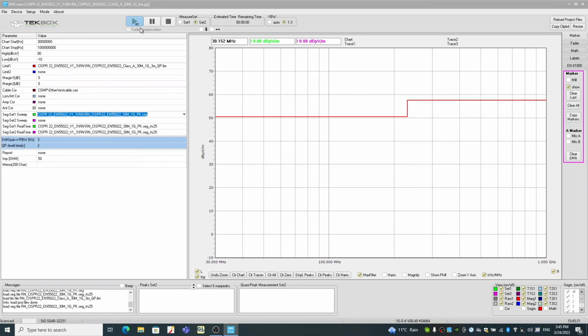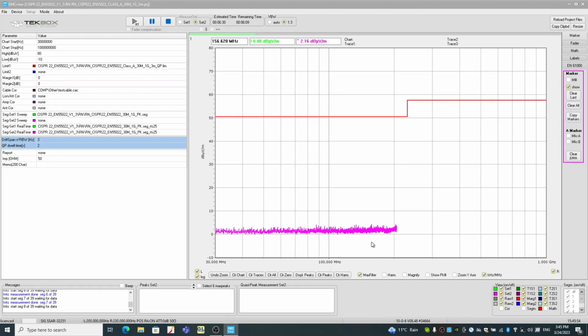Okay, so now let's perform the ambient scan first. When I click, the spectrum analyzer started scanning, and as you can see, because it is a real-time spectrum analyzer, the scanning speed is extremely fast - just as we spoke, it's already done. It doesn't take longer than 1 minute to complete the scan, all from 30 megahertz all the way up to 1 gigahertz. That's why we always prefer to use a real-time spectrum analyzer these days, because it just saves lots of time.